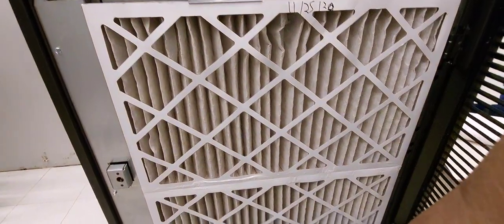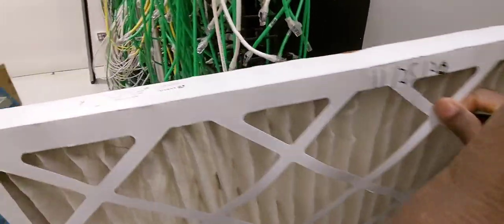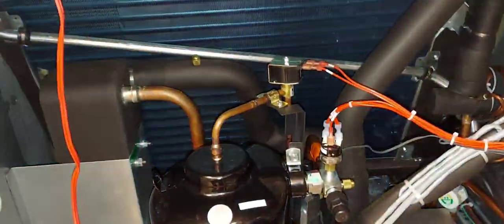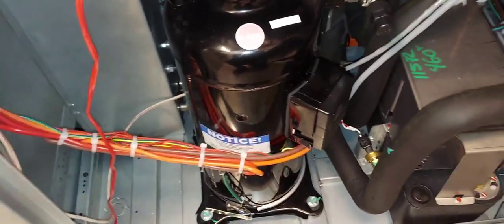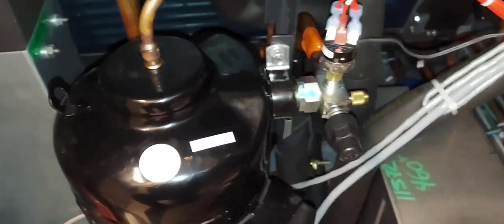Here is your air filter — and if you know filters, the arrow should be installed facing the unit. Here is your evaporator coil. This is a water-cooled unit, so this is your brazed-plate water-cooled condenser. Here is your modulating scroll compressor — I'll show you why I say it's modulating when we do some manual testing in a little bit.